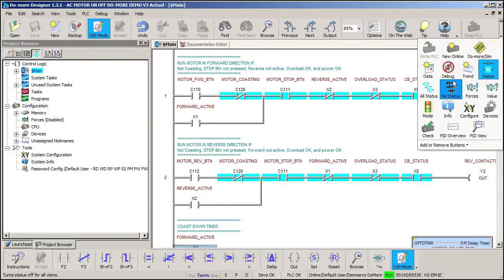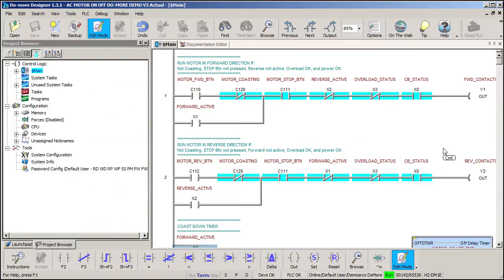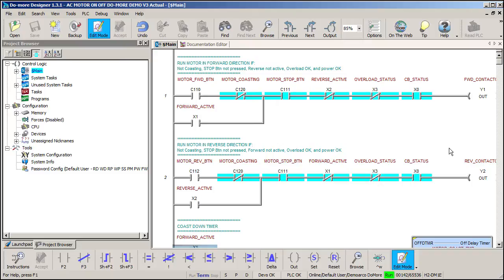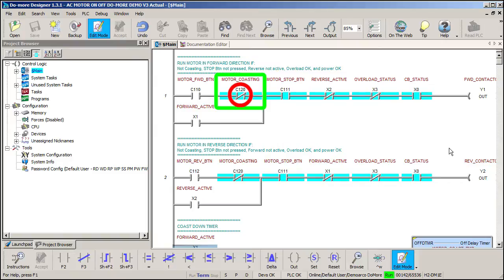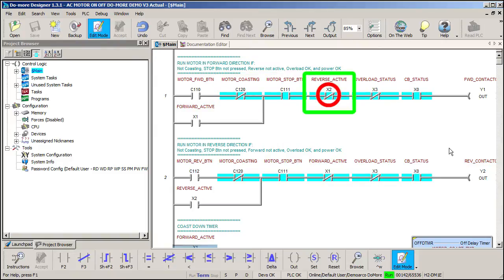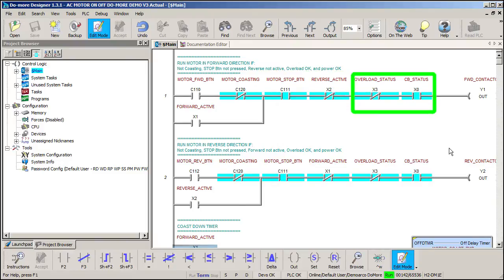If we turn on status monitoring, then these blue highlights mean the contacts are active. When all the contacts between the left and the right side are lit, the power is flowing to the output coil. So this tells us that the forward button is not being pressed. The motor is not coasting. The normally closed stop button hasn't broken the circuit. The reverse contact is not active and the power and the overload are good to go.